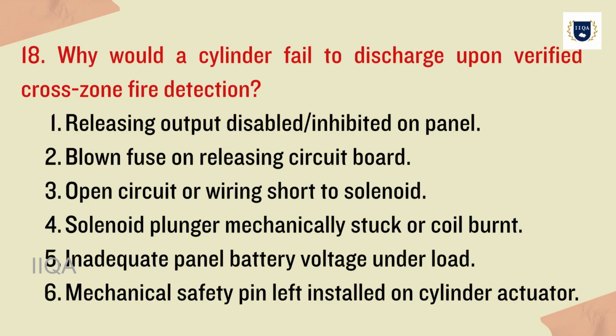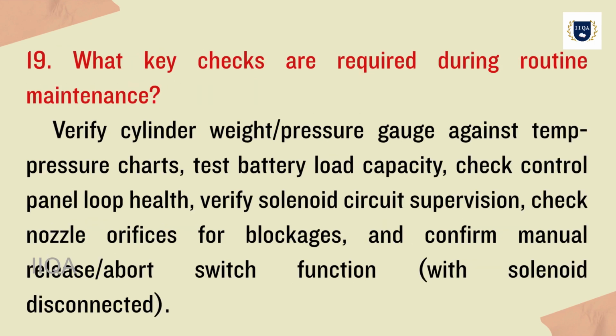18. Why would a cylinder fail to discharge upon verified cross-zone fire detection? 1. Releasing output disabled or inhibited on the panel. 2. Blown fuse on the releasing circuit board. 3. Open circuit or wiring short to the solenoid. 4. Solenoid plunger mechanically stuck or coil burnt. 5. Inadequate panel battery voltage under load. 6. Mechanical safety pin left installed on the cylinder actuator.